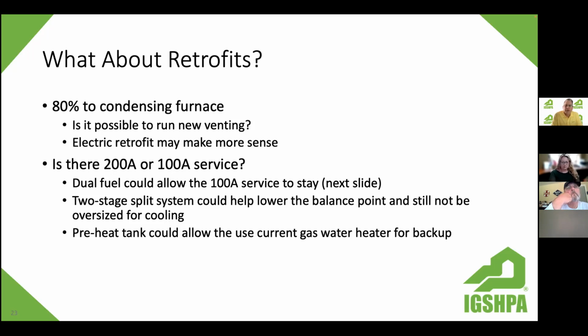It's kind of unfortunate because it's really a nice way to go to provide geothermal and a ramp up potentially later on to all electric. And with some of the two-stage systems that are available, you may be able to upsize the equipment a little bit and still not be oversized for cooling. So that helps us with our balance point. On a dual fuel system, we won't be running that gas furnace as much for backup.